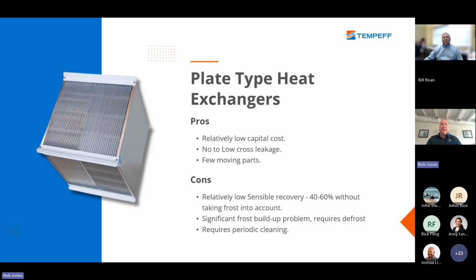The first one is a plate type heat exchanger. This is very common in residential applications. The pros of it is it's a relatively low capital cost. It has no to low cross leakage, and it has few moving parts, so maintenance is okay. The cons, it has relative low sensible recovery of 40 to 60%, and that's without taking frost into account.